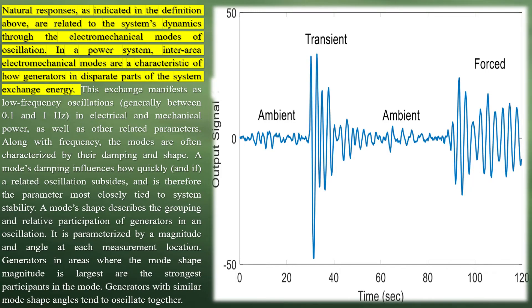Analysis: utilities use the frequency response analysis tool FRAT for frequency response analysis. FRAT is an interactive application to perform frequency response analysis methodology. Baselining: the FRAT database has an extensive system event log going back to 2008. This log creates the opportunity to evaluate frequency response trends over many years. Trending frequency response is important for tracking the impact that the changing generation resource mix has on frequency response. Utilities can perform correlation analysis between observed frequency response and generation resource mix — hydro, wind, etc. For many utilities there is a strong correlation between available hydro generation capacity and frequency response performance.